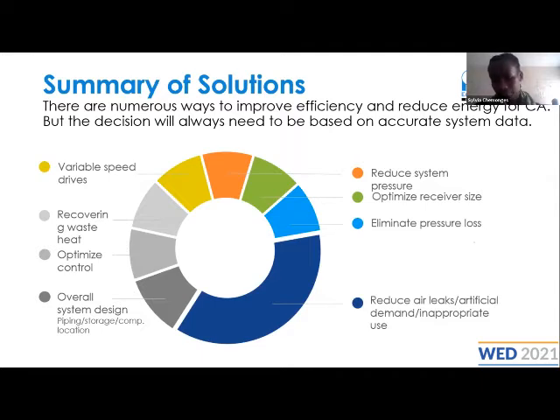Then for companies that may need to reuse the heat that's being generated, we said we lose a lot of energy in terms of heat from compressed air systems. You can consider recovery. That would be through, as I said, using the energy from the hot air to heat up spaces, or using the hot water to heat up other products, to minimize your energy consumption. Variable speed drives are very energy efficient compressors. 90% of our companies that carry out manufacturing have a possibility of using a variable speed drive. So there's a big section of this that needs to be considered over time. Most people still haven't gotten to that point yet, but it's getting there with time.